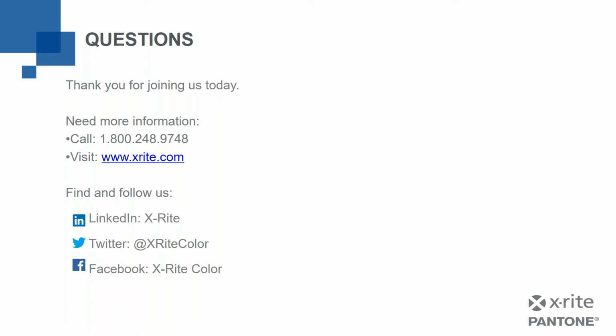So how frequently should profiles be made? Every week, every month? You can do it more often than monthly. That's 30 days is the way the software is set. The instrument and your QC software will warn you as you start to approach the fact that your profile on your instrument's about to expire. So 30 days is our recommendation.